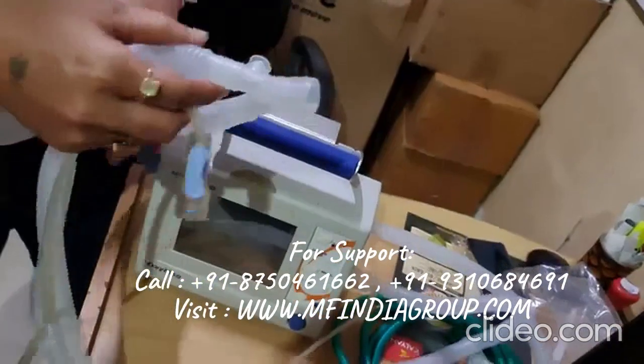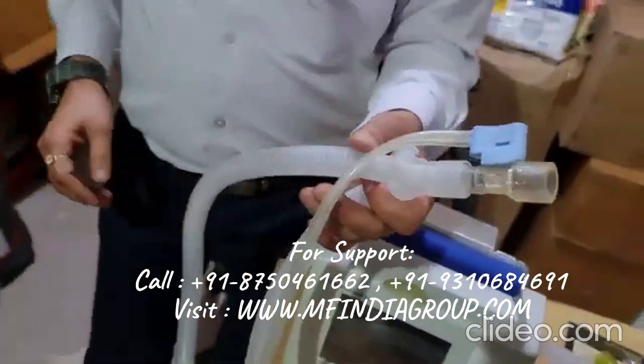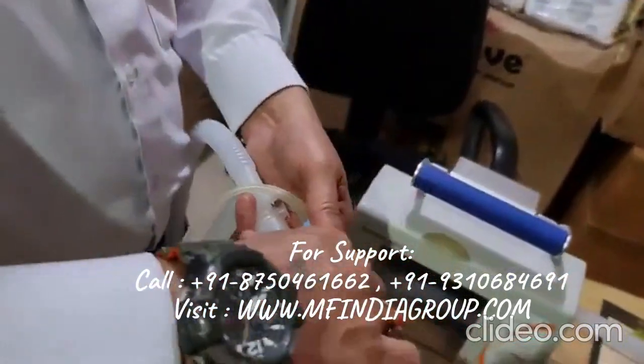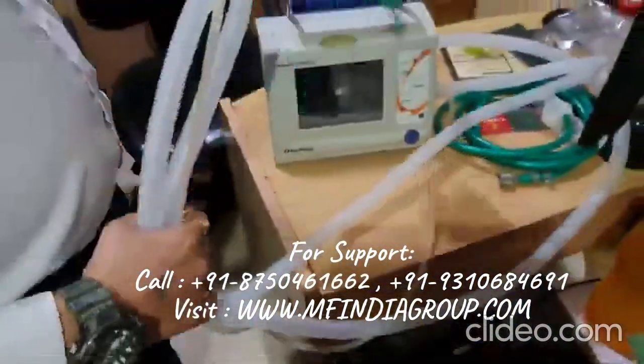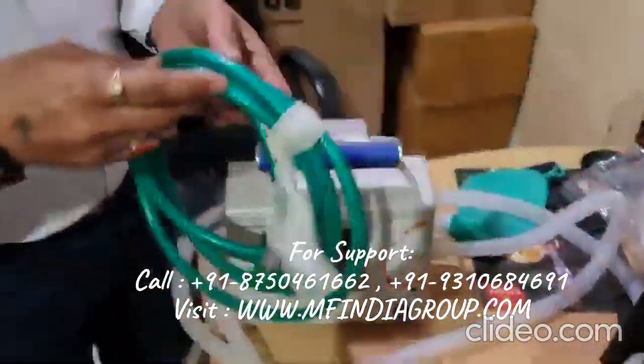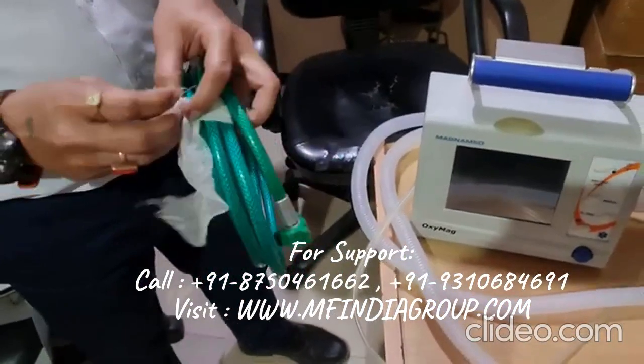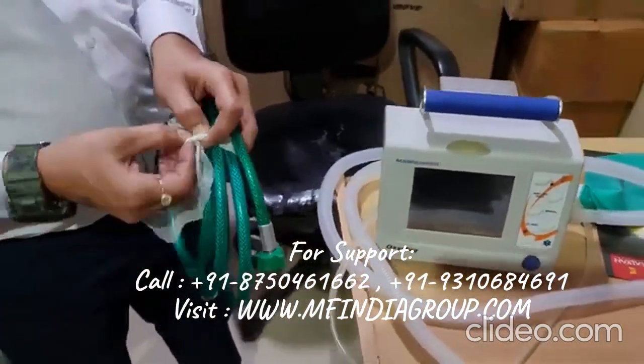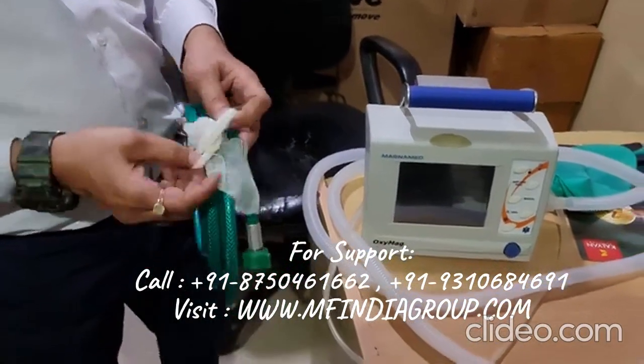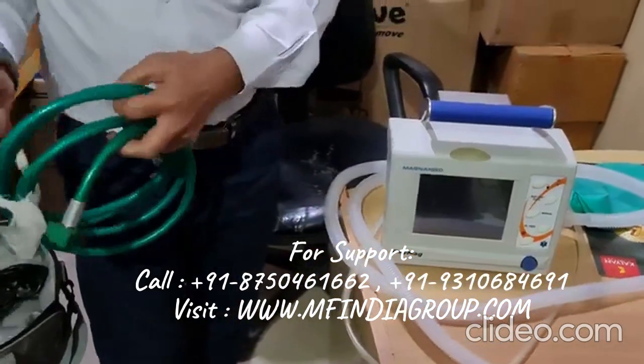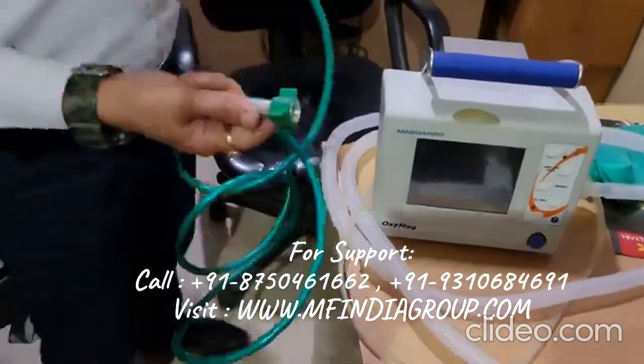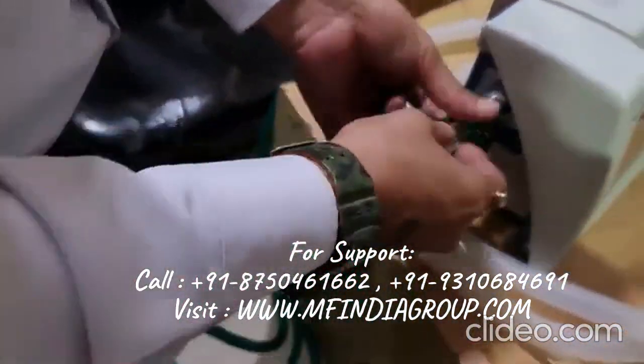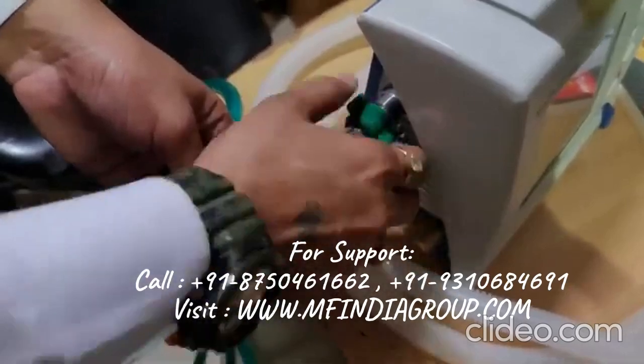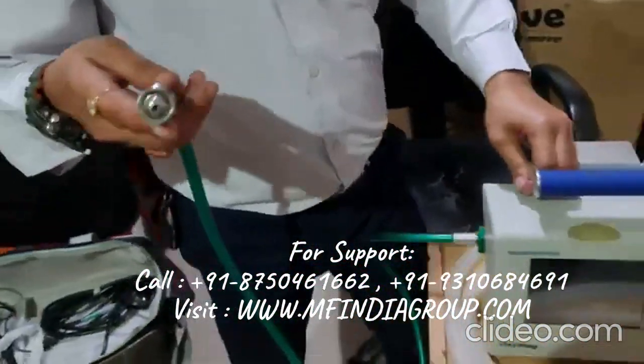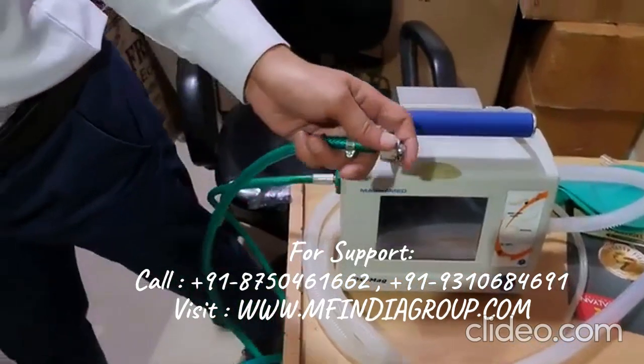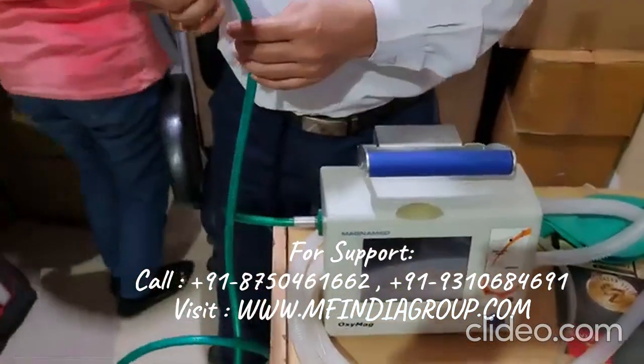And this other end of the flow sensor you can connect here. As a test lung, you can connect this rebreathing bag or any test lung here. This is the high pressure oxygen tubing. You can hand tighten this, no need for any spanner or something like that. This connector will go to the regulator or central line, and you can connect it to the central line oxygen.